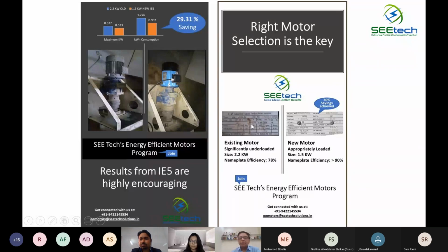Then this is how the savings were there, and around 30% savings were obtained. But if you compare their nameplate efficiencies, you will not find that the saving potential is so high, because at full load in the nameplate you get full load efficiency, at almost 100% loading. At 100% loading, you will find that the difference between IE1 or IE5 is hardly 3 to 3.5%, and you will calculate this 3 to 3.5% in your payback, and then you will find that the energy efficient motors are not at all feasible.